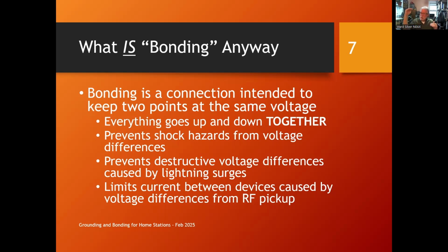Why does current flow? Because there's a voltage difference. And if you can zero out the voltage difference so that everything's going up and down together from that lightning surge, then there's no current flow between the different pieces of equipment. And that's what causes the trouble. It's not the voltage, it's the current. But the voltage causes the current to flow. So by minimizing voltage differences, you minimize current flow. And that leads to the fourth point up there, that RF pickup in your station from the nearby antennas causes current to flow between the devices in your station. Why? Because it induces a voltage difference between the different pieces of equipment. And that's what causes RFI, is that current that flows because of the voltage differences between the pieces of equipment. If you can minimize that voltage difference, you minimize the current that flows, and that minimizes RFI in your station. So bonding is good.